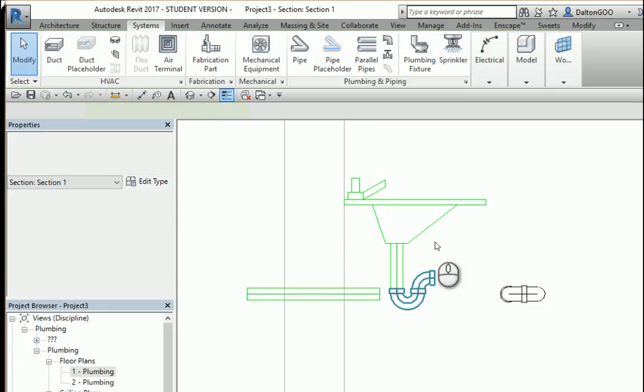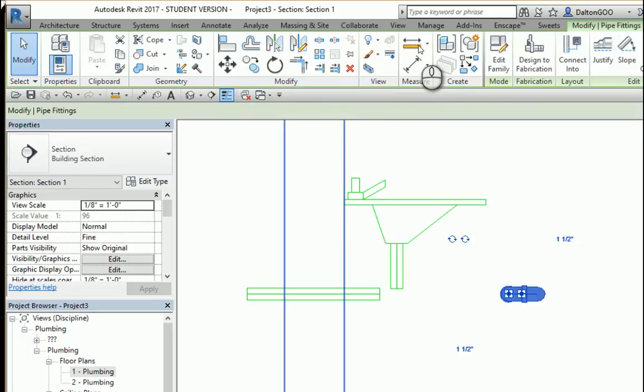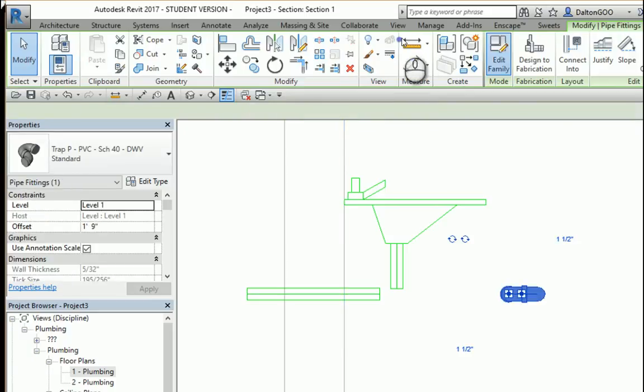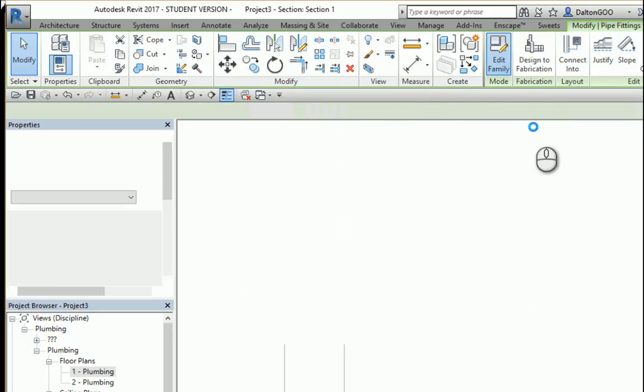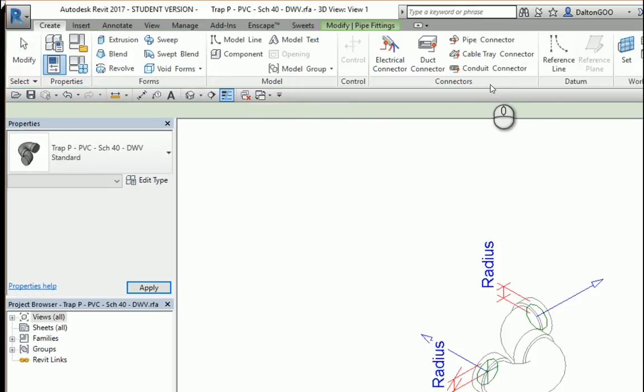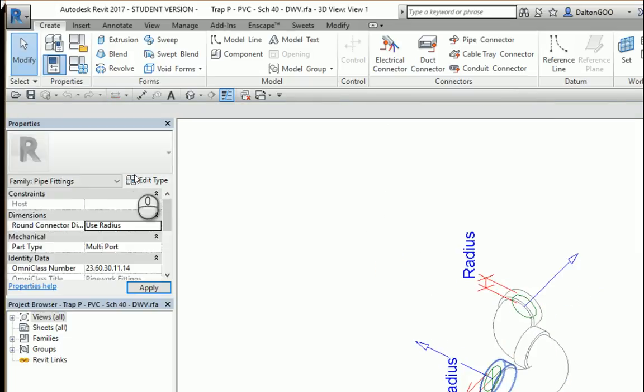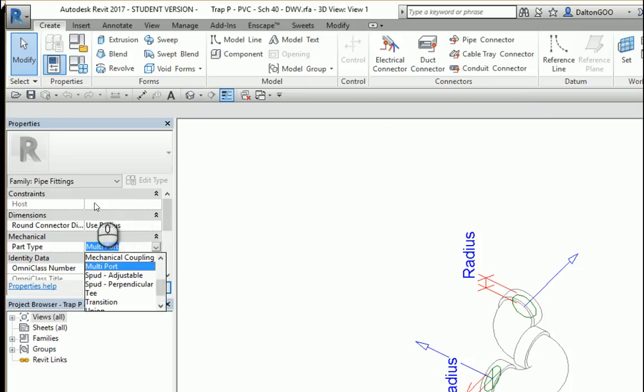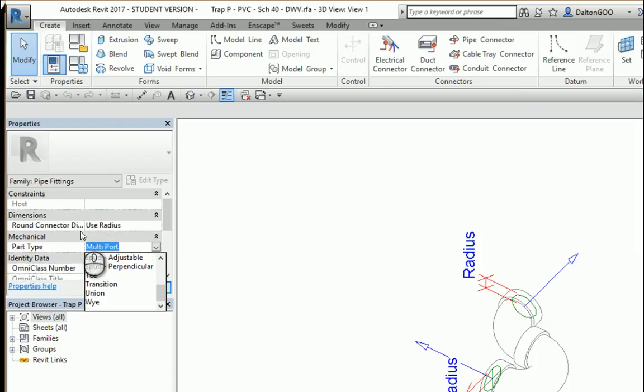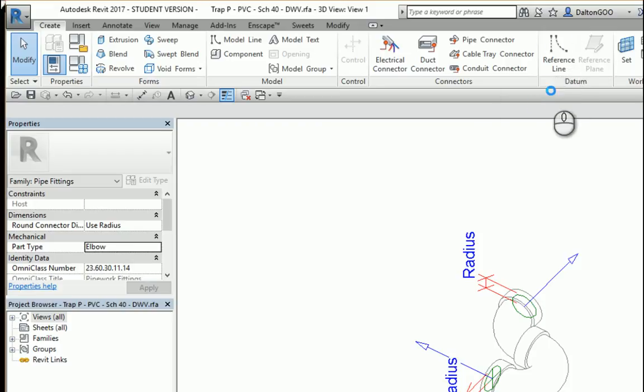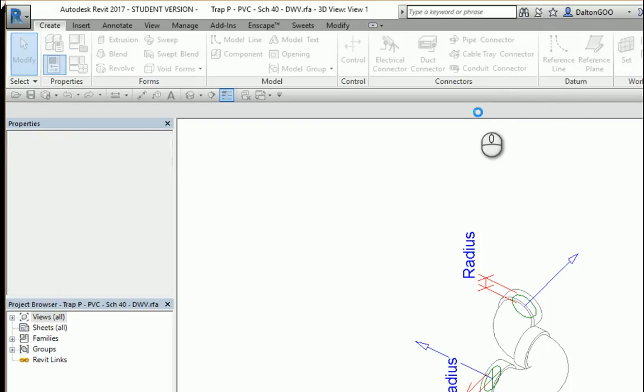So if you go into the family, edit it. Here's our part. I want to come over here to multiport. That's the part type, and that's where it's going to put it in what category. We don't want it as a multiport. We want it as an elbow. Put apply, load in the project, and just overwrite the existing.